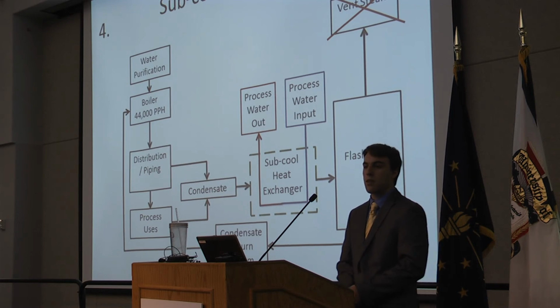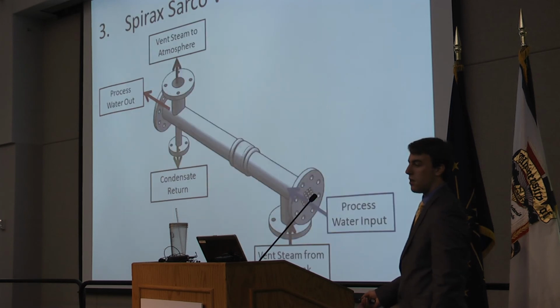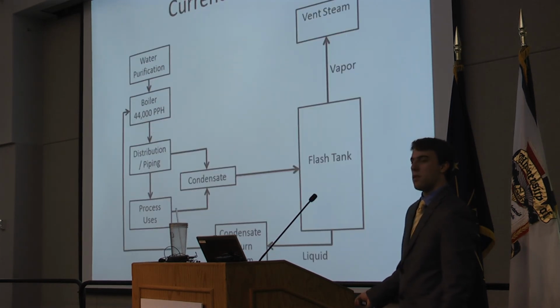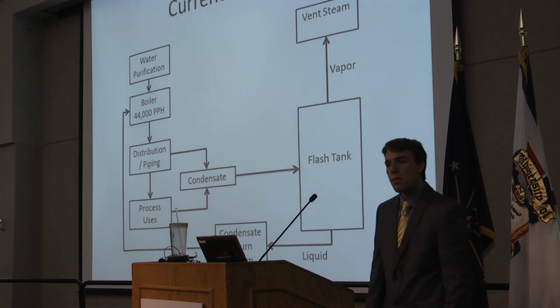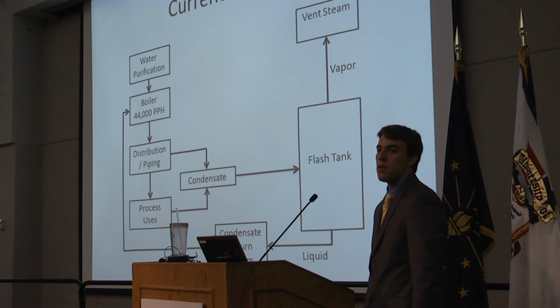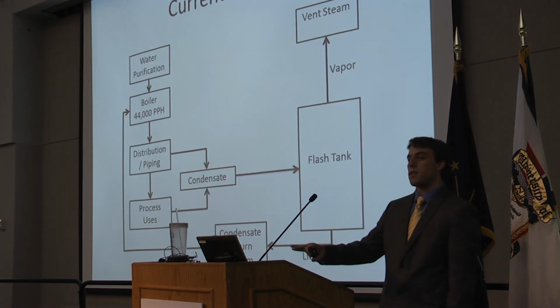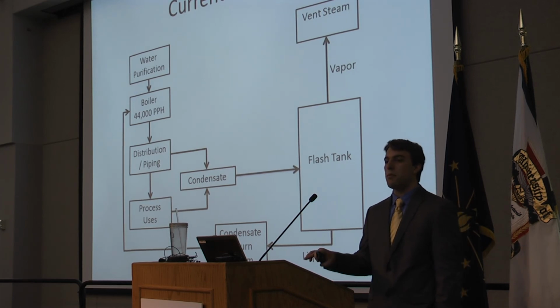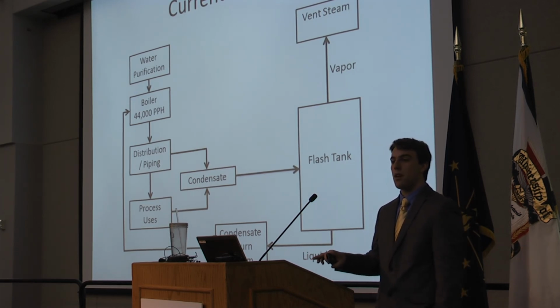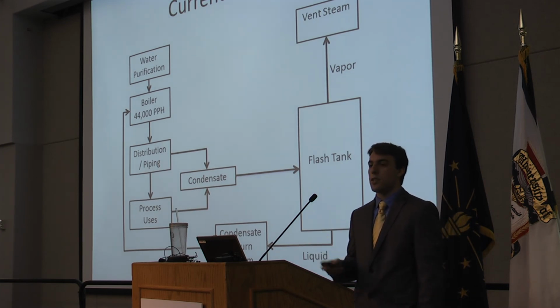Luis, great job. Thank you. Could you go back to the first diagram where you describe the steam process, please? Perhaps you mentioned that and I missed it, sorry. But what percent goes to the atmosphere? Yeah. In the high pressure, there's 2 different tanks, a medium pressure and a high pressure tank. In the medium pressure, it's 8% of that condensate that escapes as flash steam, and then in the high pressure, it's 13%. Okay.